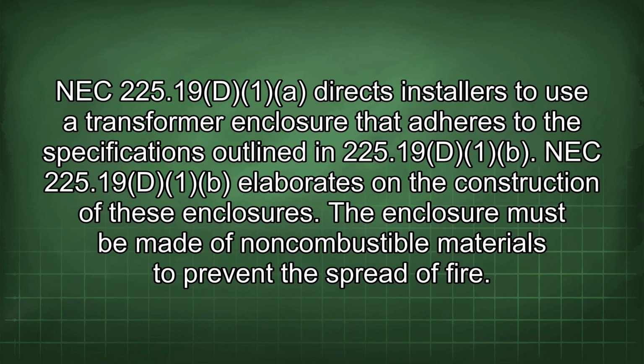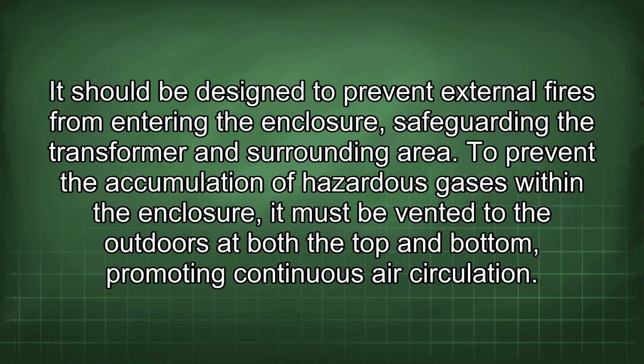NEC 225.19(D)(1)(a) directs installers to use a transformer enclosure that adheres to the specifications outlined in 225.19(D)(1)(b). The NEC 225.19(D)(1)(b) elaborates on the construction of these enclosures. The enclosure must be made of non-combustible materials to prevent the spread of fire. It should be designed to prevent external fires from entering the enclosure, safeguarding the transformer and surrounding area.